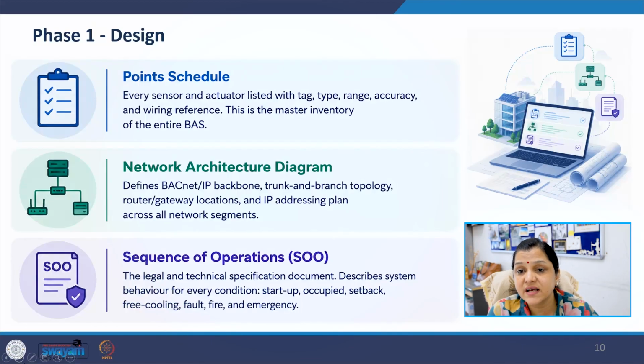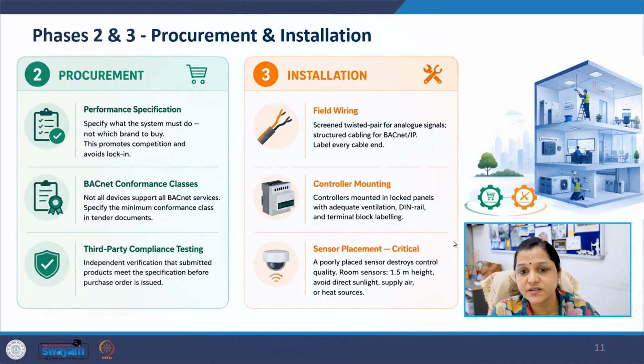A poorly prepared design phase creates confusion during installation and commissioning. Therefore, detailed, well-designed planning is essential. Next is procurement and installation. The procurement phase should focus on performance specification instead of specifying a particular brand. The designer should specify functional requirements. This promotes competition and prevents vendor lock-in. It is also important to define minimum BACnet conformance requirements because not all devices support the same services. Third-party compliance testing is often useful before procurement approval.